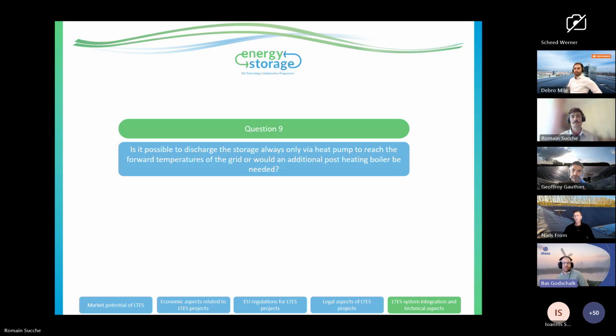It's a tricky question because it strongly depends on a number of variables, like what is the supply temperature of the heat you have in excess. Then you need to store it, and then it's the question, what is the volume, how much is needed, and at which temperature you can discharge it. Secondly, it's also important to know what's exactly the required temperature in the grid itself. So for district heating systems, it's maybe quite high. We also design high temperature ATES systems for greenhouses. They can often use a lower temperature in their heating network.